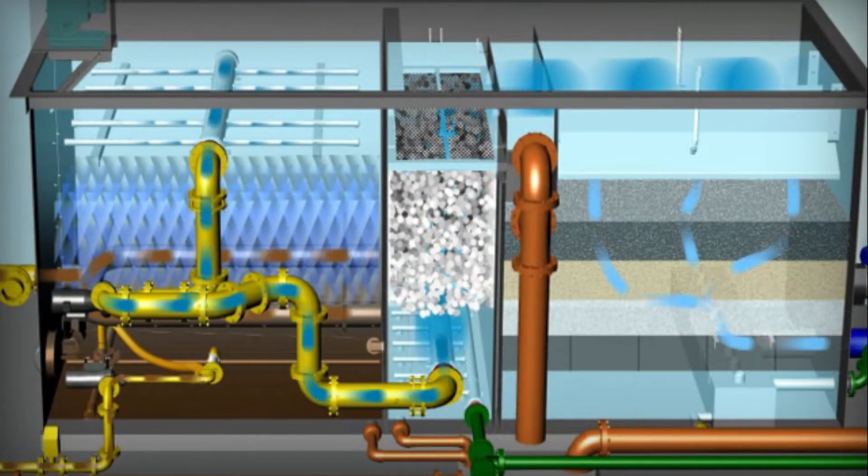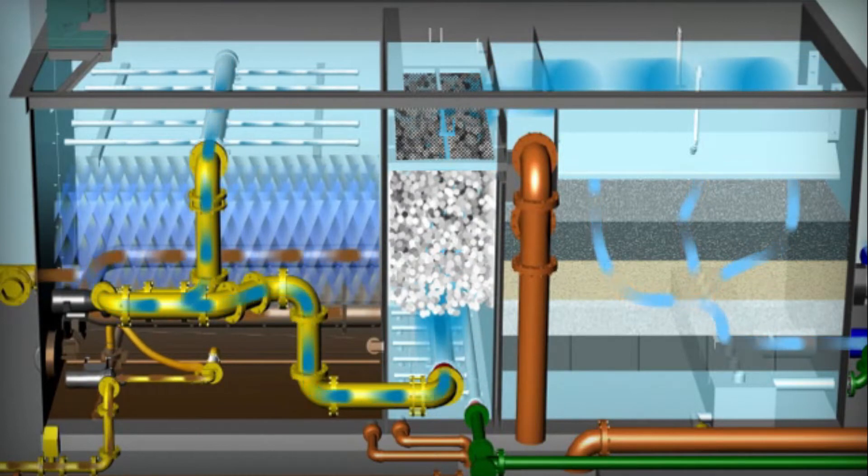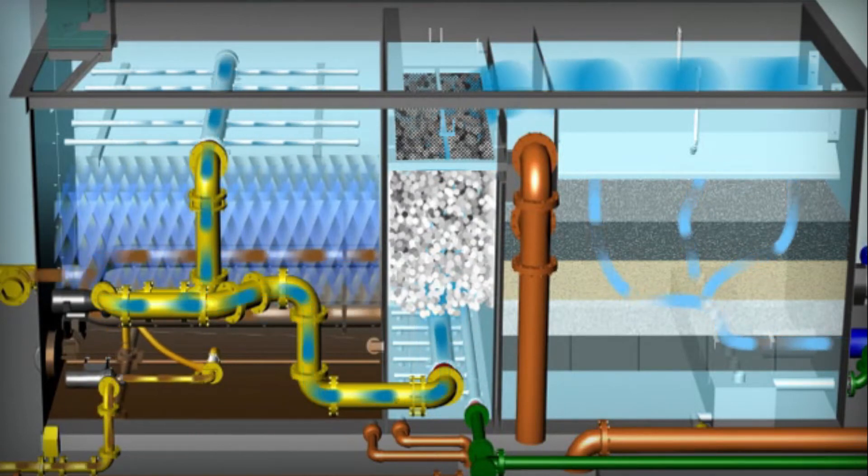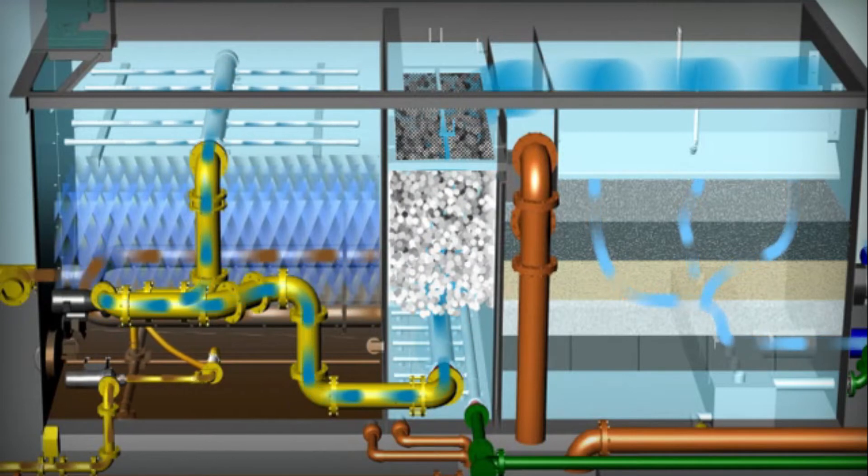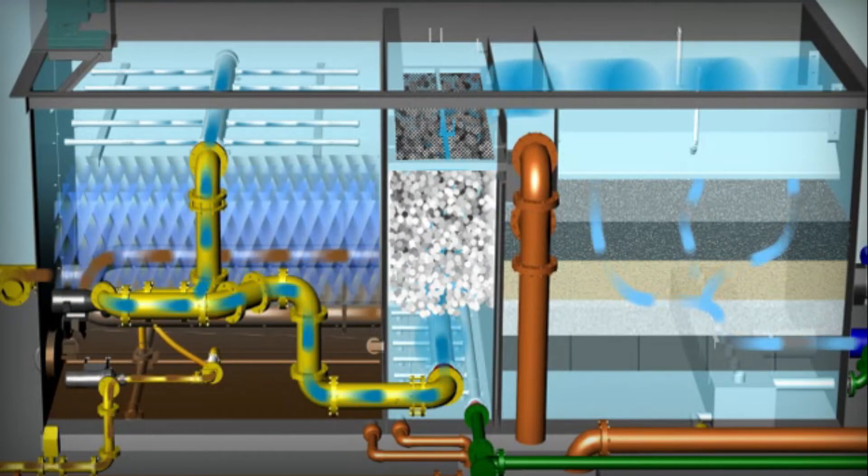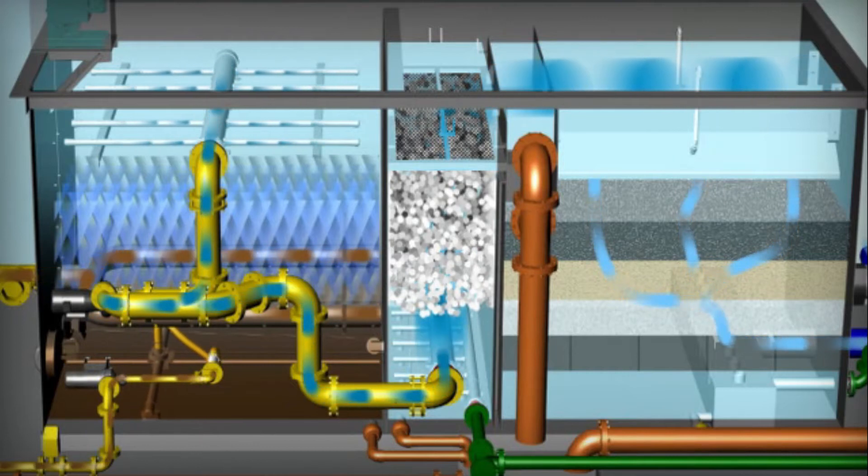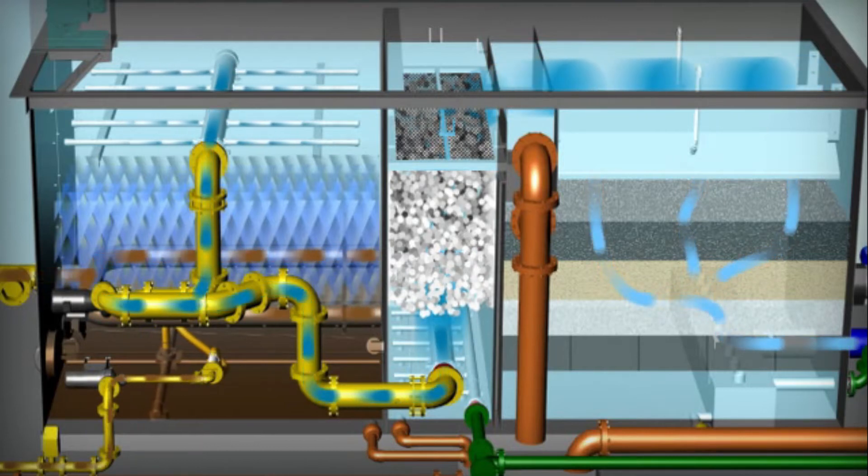Clarified water enters the bottom of the adsorption clarifier and flows upward through a bed of buoyant media, where additional flocculation assists with solids reduction. The media is specially manufactured with scarified surfaces for improved floc retention.